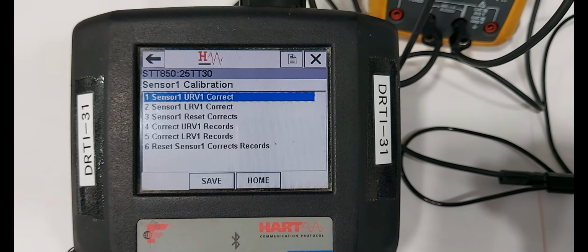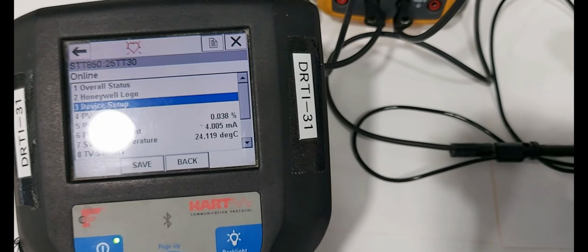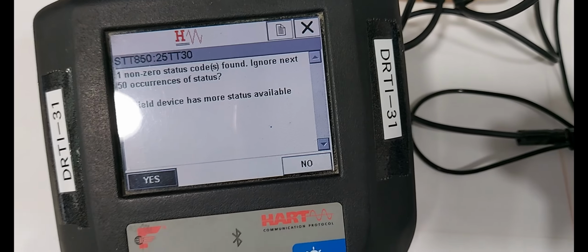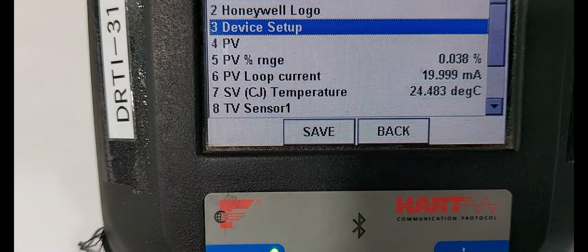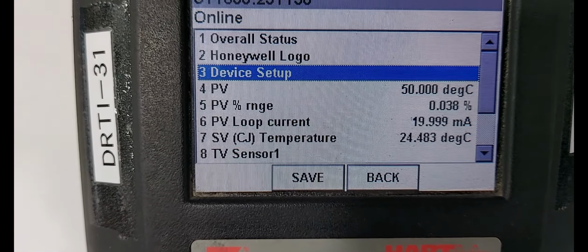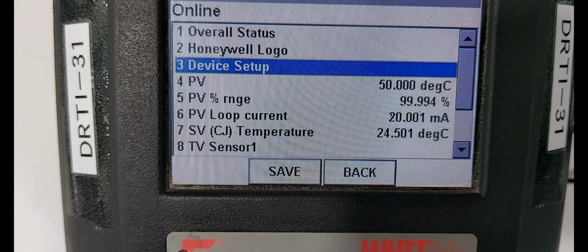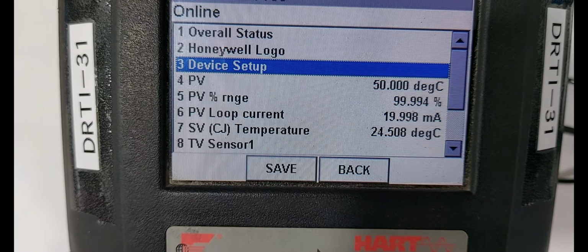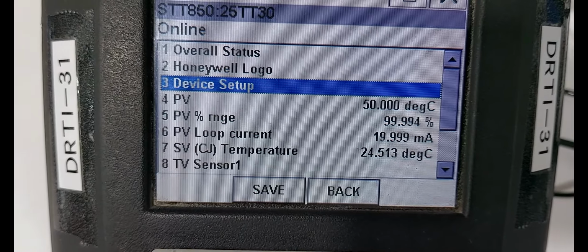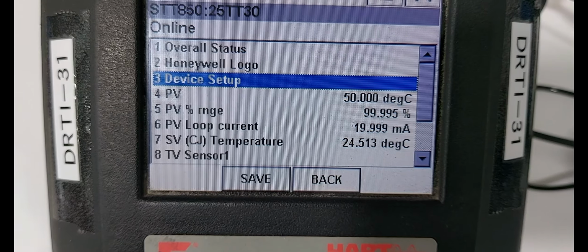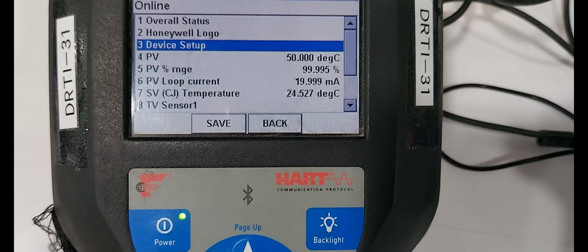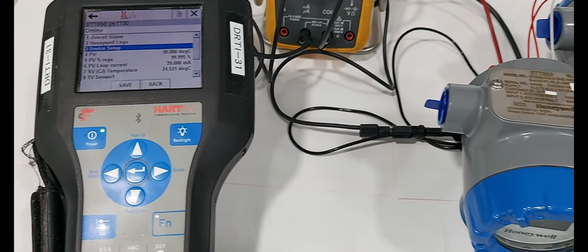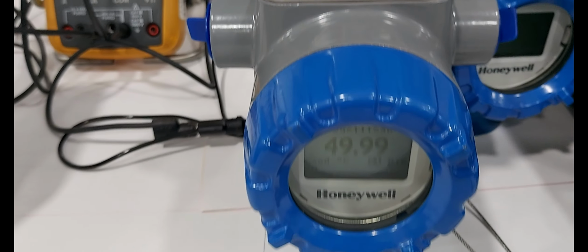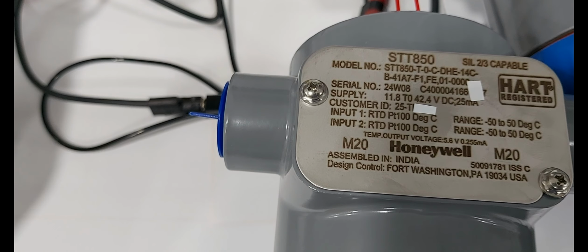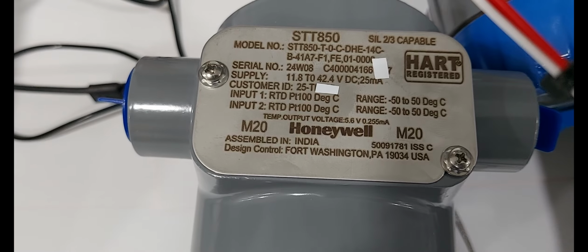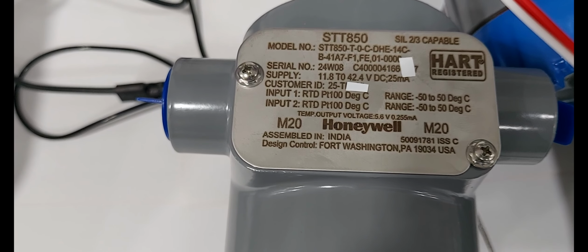Automatic controller, then OK. Home menu. Yes. Check the value. Now the PV value is showing 50 degrees, the percentage is showing 99.99 percent, and the loop current is showing 19.999 milliamps DC. Now it has reached 20. This is the normal calibration procedure for the Honeywell STT850 HART protocol temperature transmitter calibration scenario.